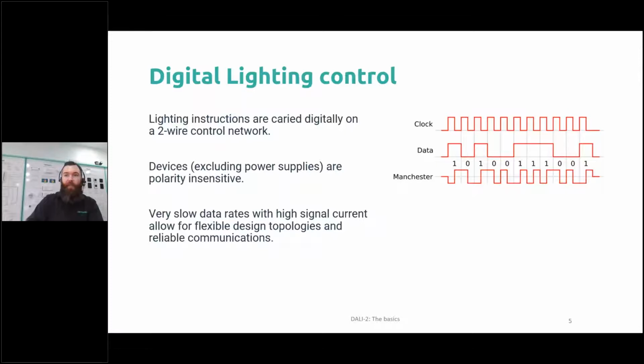Okay, so you don't have that issue of something like power line flickering, and as the light's transitioning from high to a low level, there's some sort of momentary interruption. The type of thing that happens in a real world environment. You don't have that issue because in a DALI system, you actually send a command. We say, address 1, move from your current light level to 50% over 20 seconds. And once that command's been sent, so long as it's received, it will actually start running and it will execute it. And that's worked out by every separate light in your building as well.